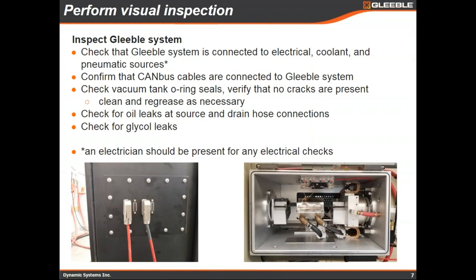Moving to the main Gleeble unit, confirm it's connected to the electrical source, the coolant source, and the hydraulic and pneumatic sources — these all go in underneath the load unit electrical box. The Gleeble will need CAN bus communication throughout the system, so the hydraulic pump, the vacuum if equipped, and any additional items using CAN bus connections shown in the bottom left picture will need to be attached — make sure they're not hanging down on the floor.